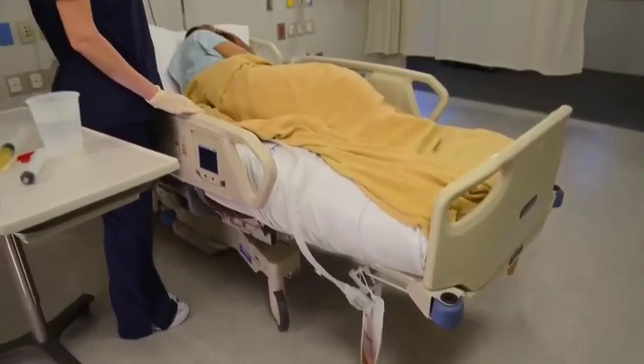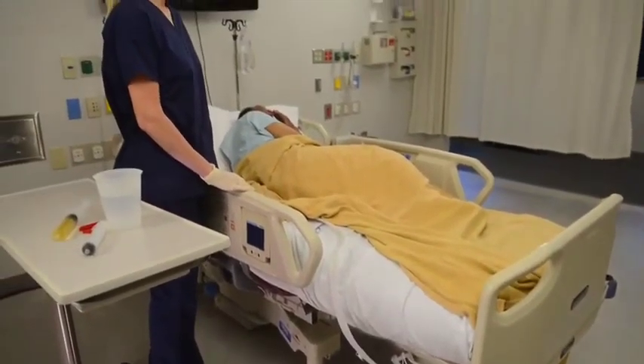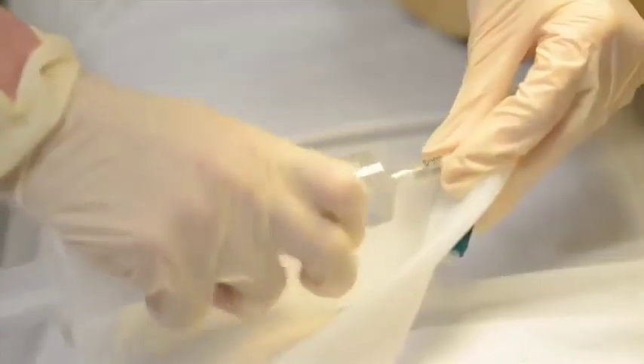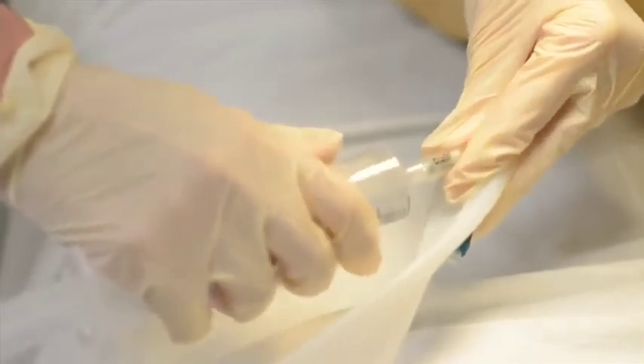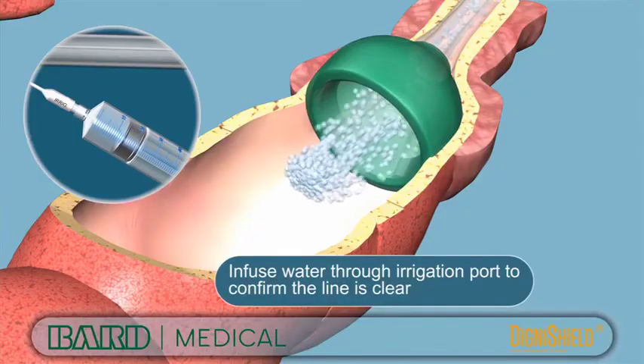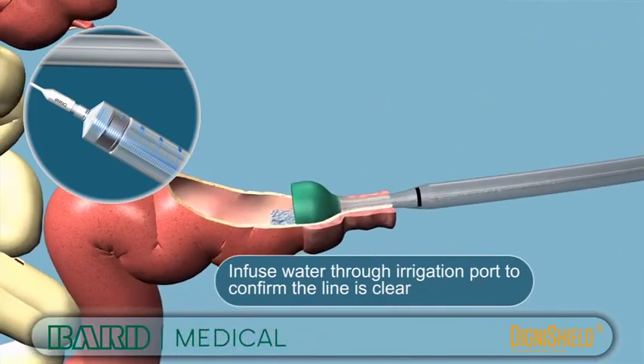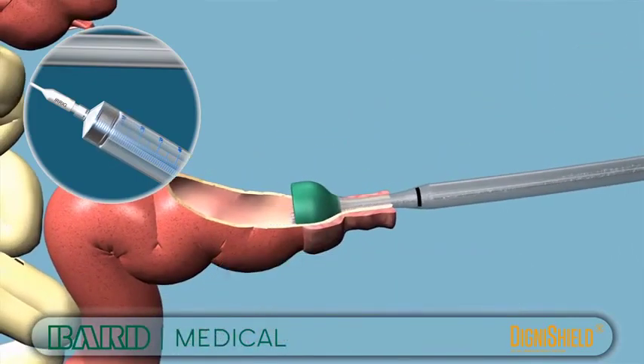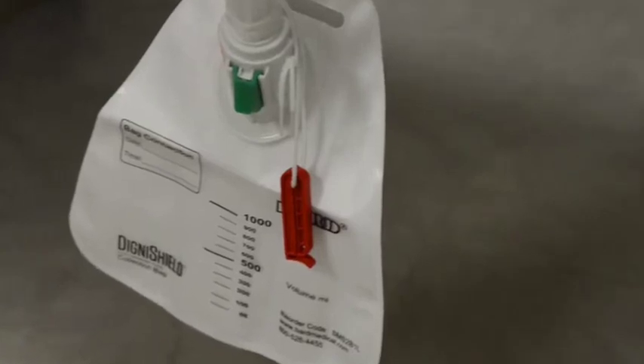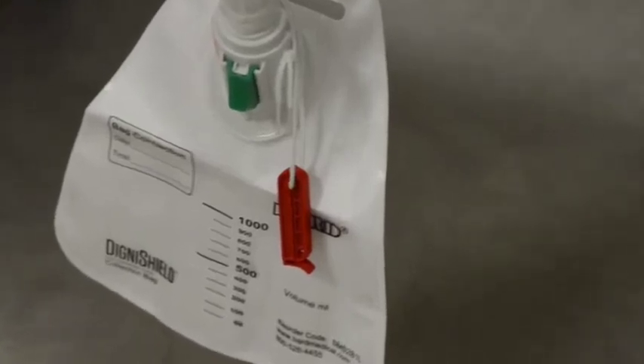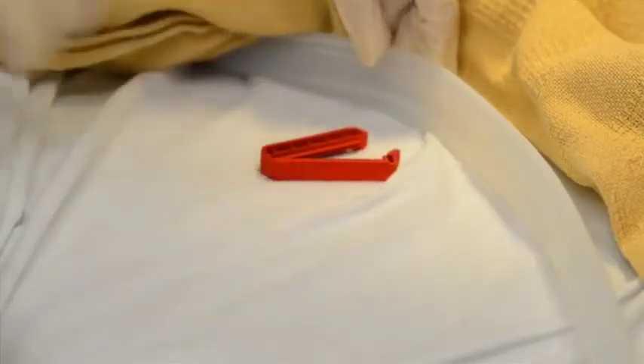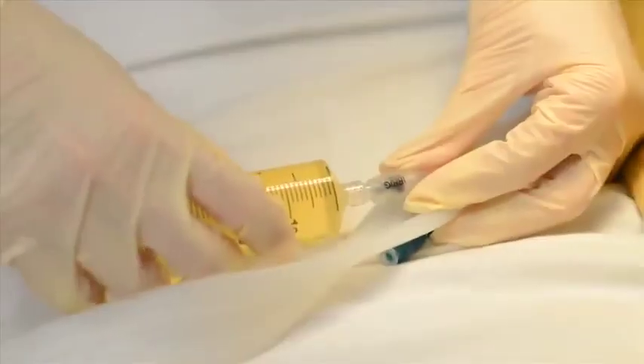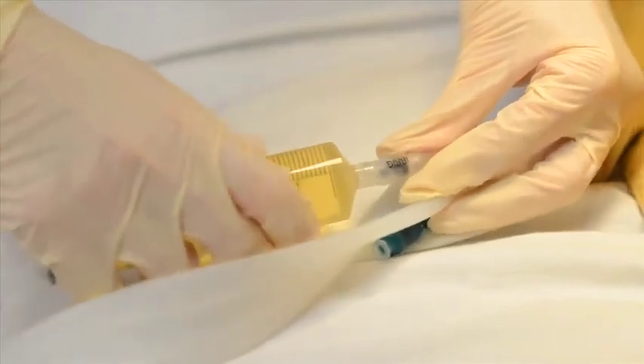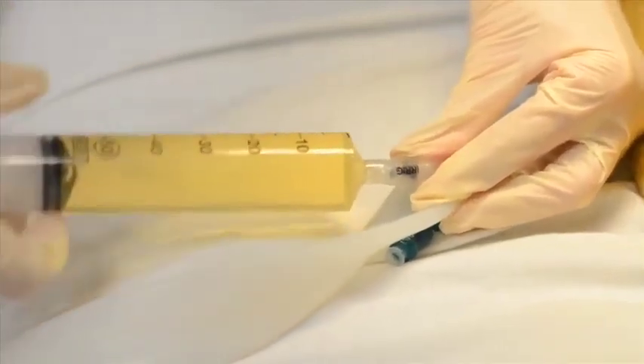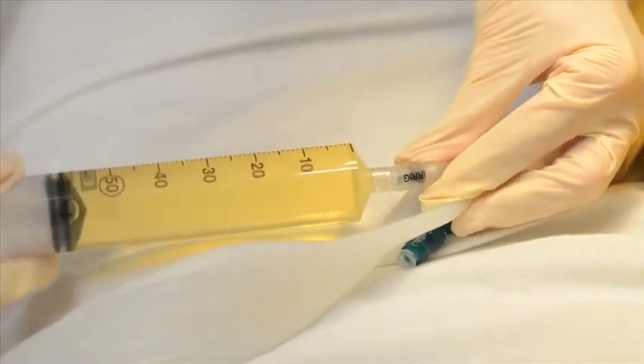Position the patient according to your facility's protocol for rectal medication delivery. Locate the clear irrigation port and confirm the line is clear by attaching a luer lock syringe to the port and flushing the system with water. Address any leakage around the cuff prior to moving forward, if present. Locate the tube clamp that comes pre-attached to the piston valve hanger string. Place it near the patient. Attach a luer lock syringe with the medication to be delivered, dosage as indicated and as prescribed by the treating physician, to the clear irrigation port.